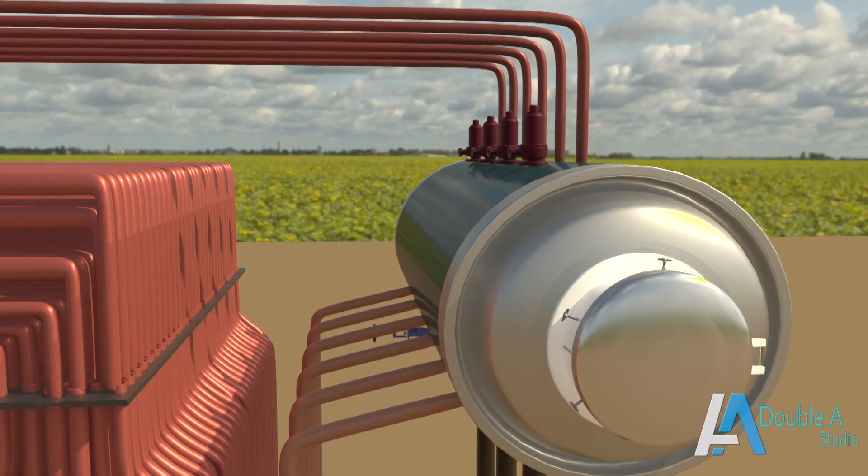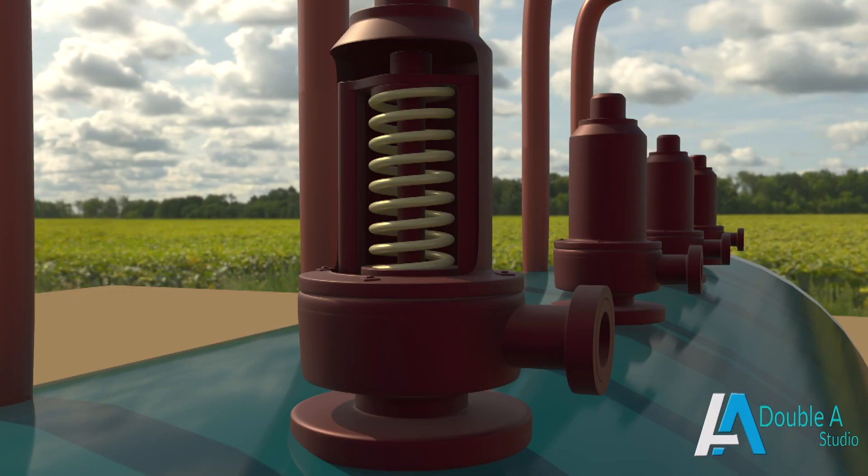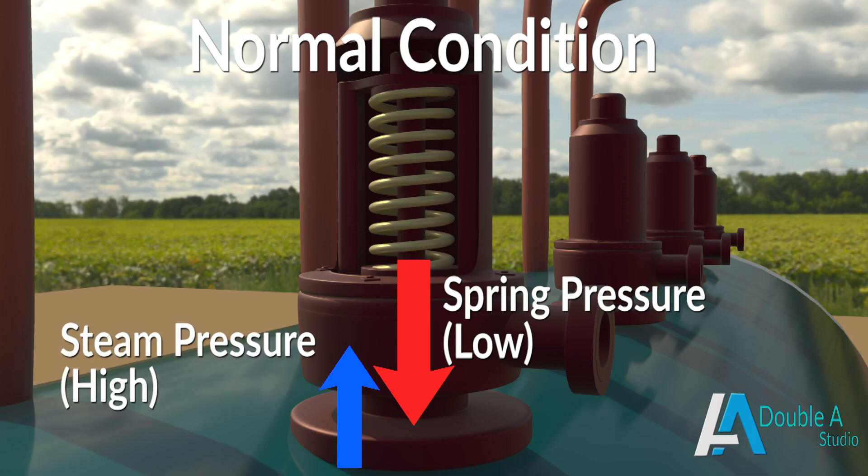The number of safety valves depends on the capacity and type of boiler. It is made up of a cast iron body. Under normal conditions, the valve is kept on its seat by spring pressure in the downward direction and remains closed until steam pressure is greater than spring pressure in the upward direction. When the boiler starts to overpressure, the valve discharges a small amount of steam, which is called simmering.